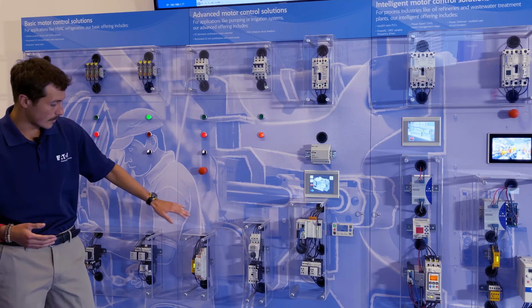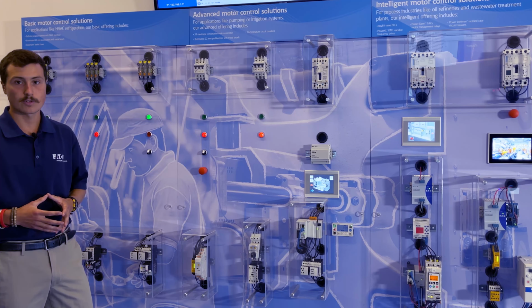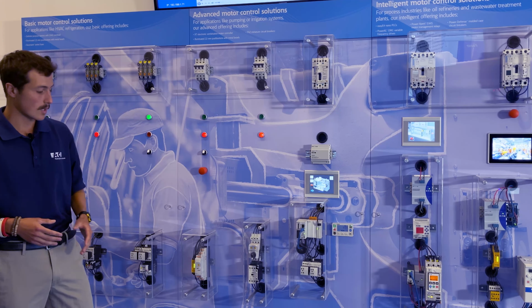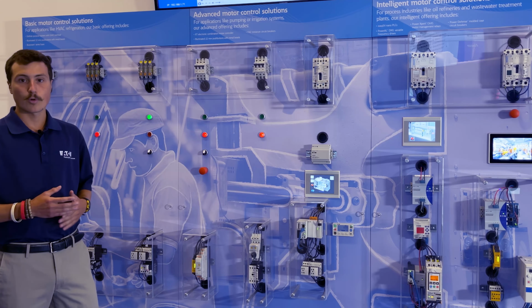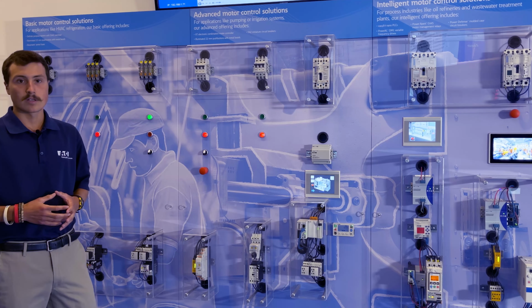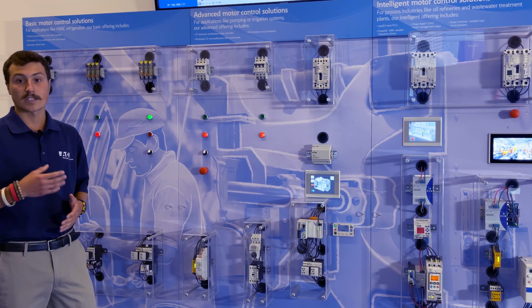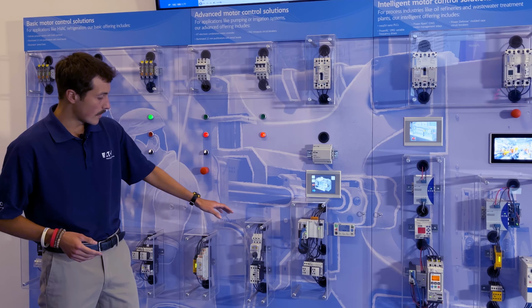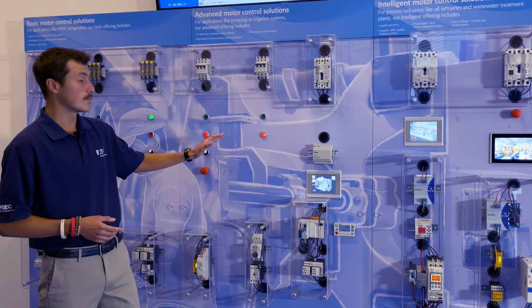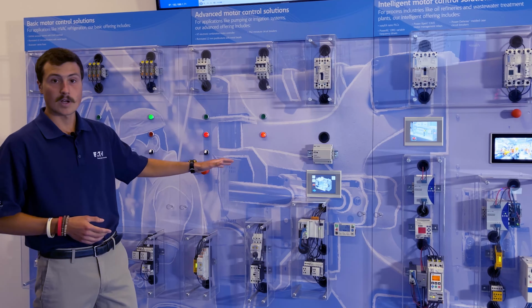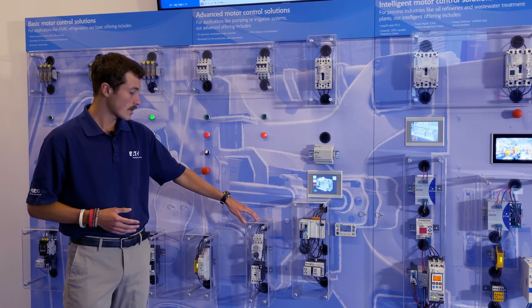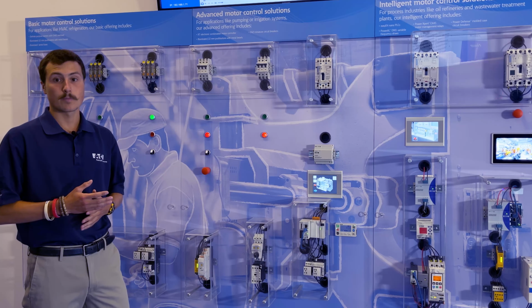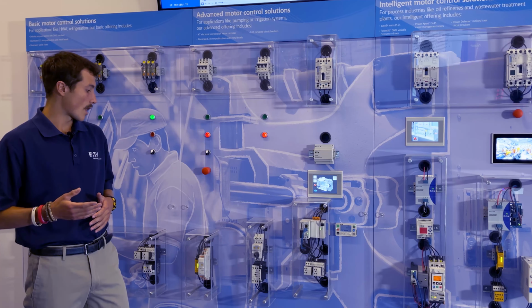Next, we have the motor starters for the more advanced motor control solutions. The first one uses Eaton's safety relay and Eaton's electronic motor starter. The electronic motor starter is more durable than the regular contactors and actually lasts up to 10 times longer. Next, the second advanced motor control solution uses an XT IEC combination motor controller along with the XT IEC manual motor starter. It's actually a solid state manual motor starter, and it's able to detect short branch circuit faults and other ground faults.